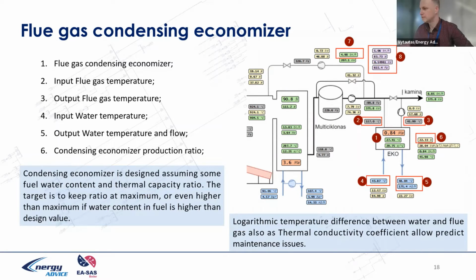So we also monitor the logarithmic temperature difference per boiler. We also monitor the flue gas path resistance, hydraulic resistance, and this information delivers a couple of things. One thing is optimization of electricity, kilowatt electricity per megawatt of thermal heat.